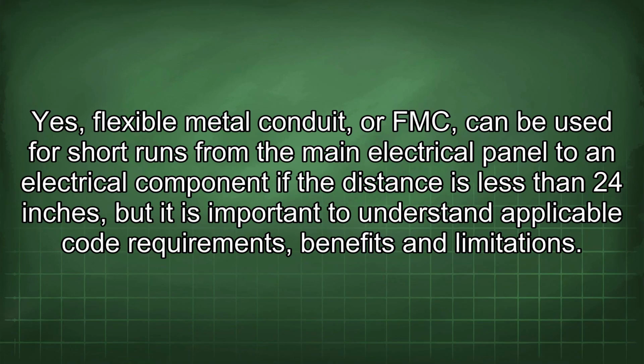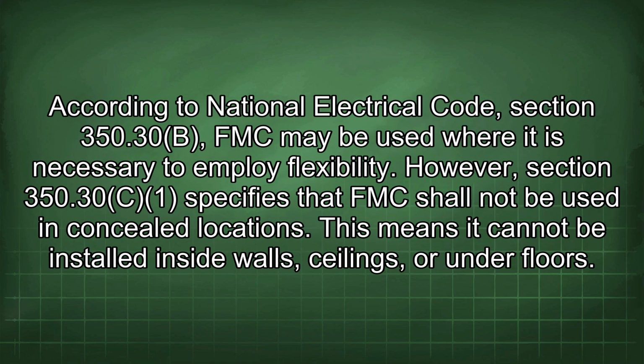Yes, flexible metal conduit, or FMC, can be used for short runs from the main electrical panel to an electrical component if the distance is less than 24 inches, but it is important to understand applicable code requirements, benefits and limitations. According to National Electrical Code, Section 350.30b, FMC may be used where it is necessary to employ flexibility. However, Section 350.30(C)(1) specifies that FMC shall not be used in concealed locations. This means it cannot be installed inside walls, ceilings, or under floors.